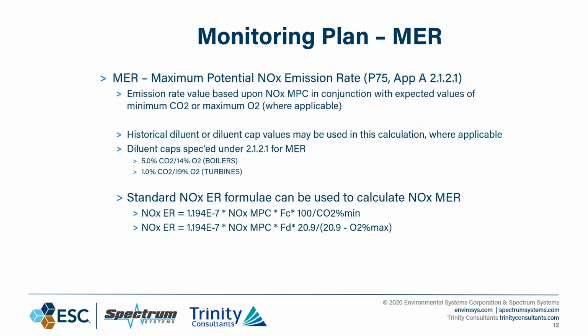And your maximum emission rate. These are your worst case emission rate values based upon your max potential in conjunction with the expected values of a minimum CO2 or maximum O2 diluent where applicable. You can also use historical diluent or diluent cap values if applicable here.